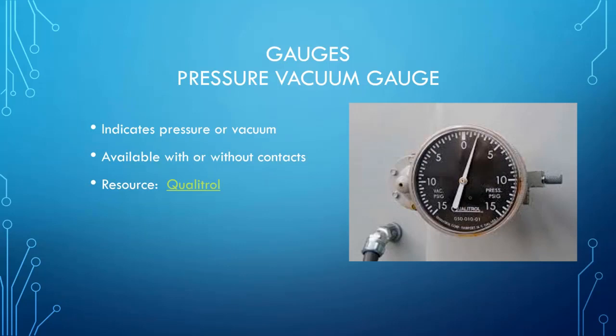And also that a positive pressure means it's not sucking in air from the outside world, which has moisture in it. So the best you can hope for is to come across a pressure vacuum gauge that shows a positive pressure. Your second choice is it shows a vacuum, which is acceptable because it means the tank is still intact. What you really don't want to run across is a transformer whose pressure vacuum gauge constantly reads zero, because that means most likely your tank has ruptured or the integrity has been compromised. And again, there's a link here to Qualitrol's website.